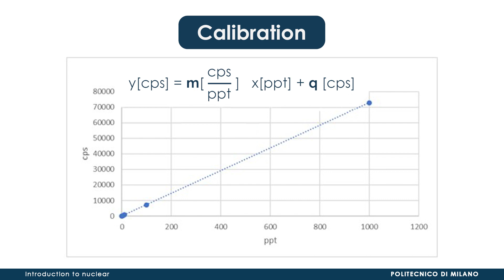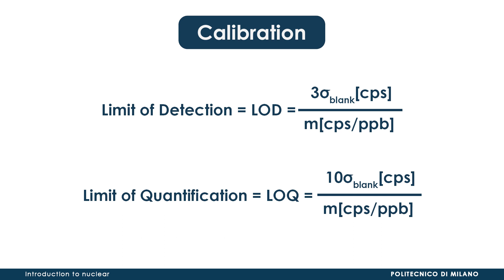The instrument has to be properly calibrated by certified standard solution, and it enables to calculate the calibration line, from which the limit of detection and the limit of quantification can be derived. The first one represents the value above which the presence of the element could be discriminated from the background, while the second one, the value above which the element concentration could be quantified. The same water sample is analyzed in a few minutes and the uranium concentration is determined, together with its isotopic ratio.